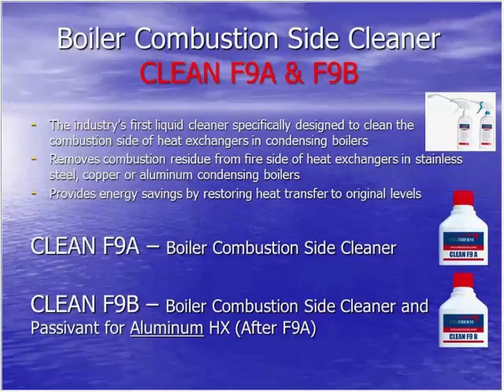aluminum condensing boilers. With condensing boilers, it seems the more they condense, obviously the more energy efficient they're running, but the more buildup there is on them too. And we also tend to see more buildup on the fire side of the heat exchanger if you're using poor quality gas, or liquid propane, which is actually quite a bit dirtier than natural gas, so you have to clean it more often. And by cleaning it, you provide energy savings by helping restore heat transfer to original levels.